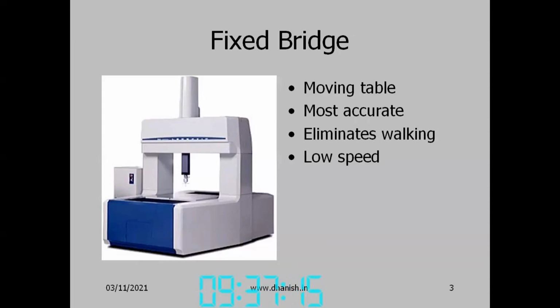Now we have to move the table. The table is heavy and usually a granite table, so moving that is not very fast. It is very slow. So inspection speeds are a little lower in the fixed bridge type of CMM, but accuracy is much better. Also, very heavy parts placed on it cannot be moved easily. It may get stuck, etc. There is a limitation on the maximum weight. Whereas in the moving bridge type CMM, you can place any part because the table is not moving. Here, since the table has to move, the weight that can be placed on it is limited.